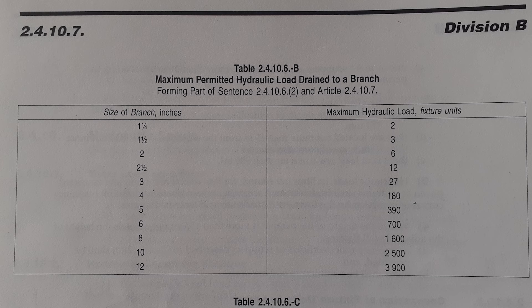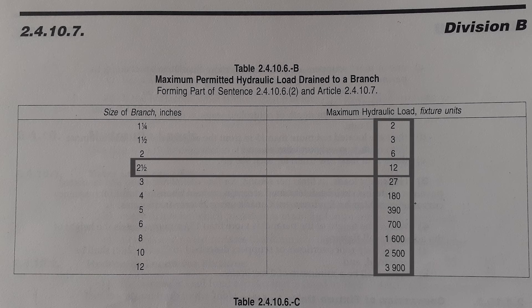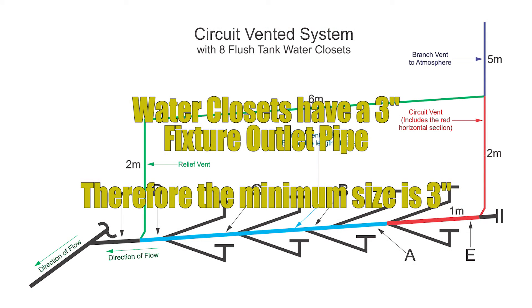Now here's a tricky one. If we look at our branch table, it says we can use 2-and-a-half-inch pipe for 12 fixture units — but that pipe size doesn't exist. On top of that, the water closet has a fixture outlet pipe of 3 inches, so pipe A needs to be 3 inches because we can't go smaller.